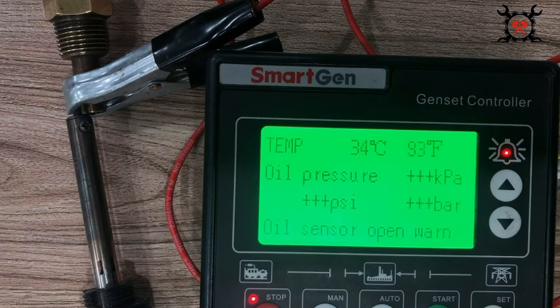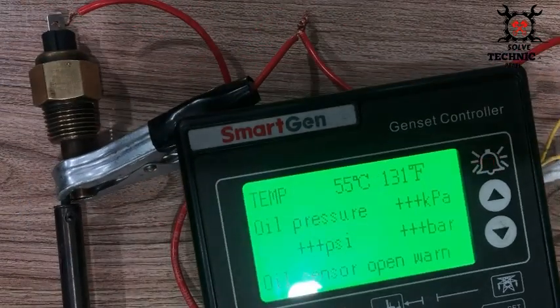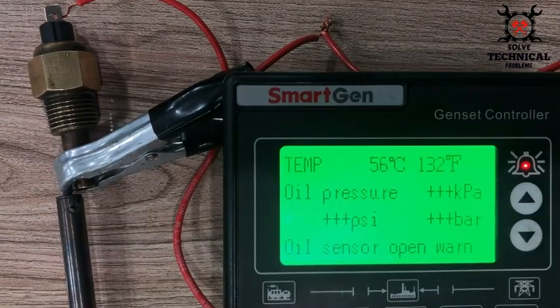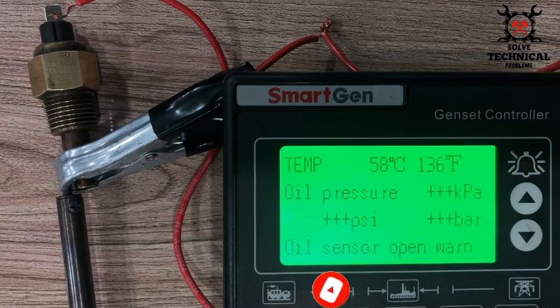We will also measure the resistance. At around 48 to 49 degrees centigrade, we will measure the resistance in the sensor and its switching point. The temperature is still increasing as the soldering iron heats up the temperature sensor, and we are measuring it with the help of this SmartGen genset controller.